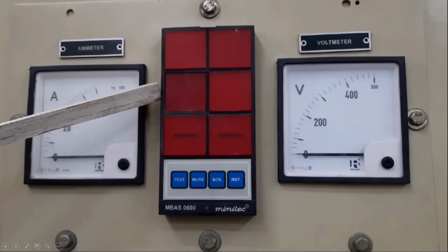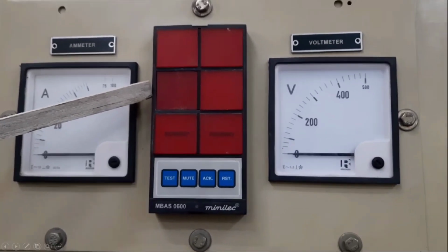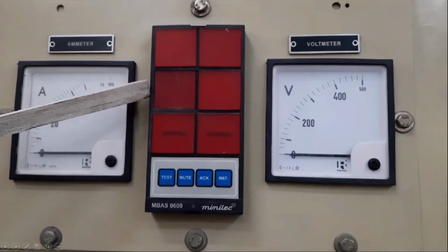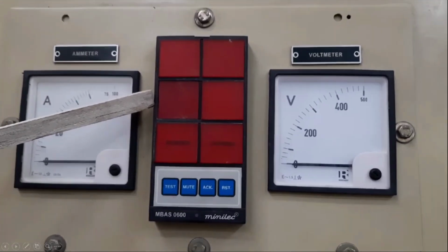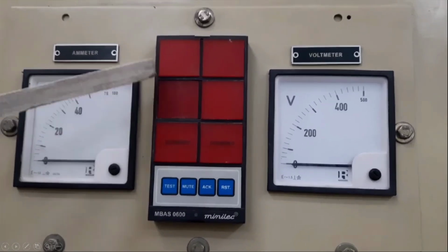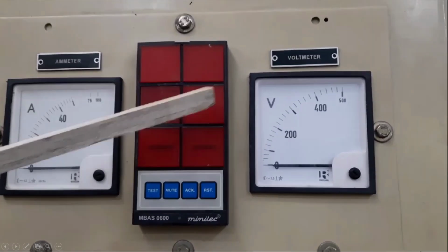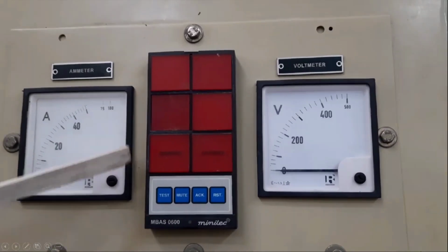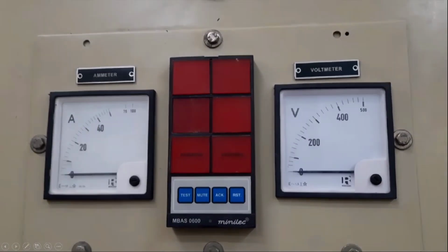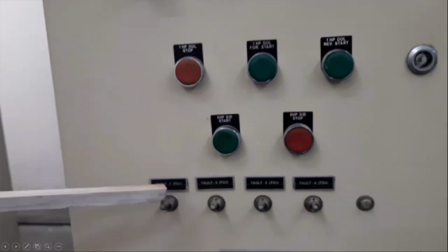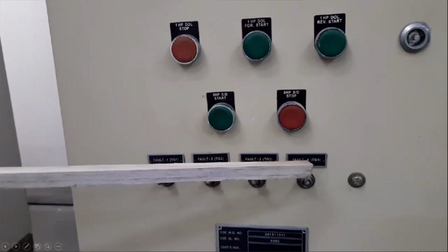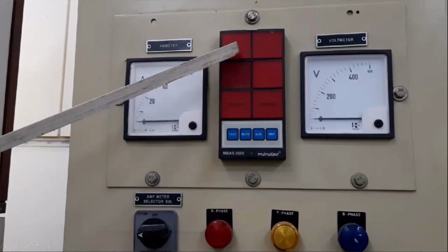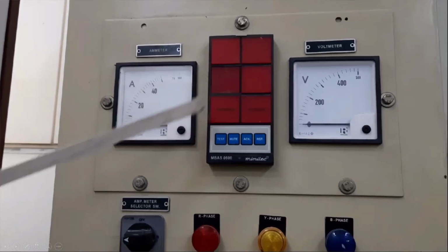Whenever there is a fault in the machine, the operator must know what is the type of fault, and at that time the panel should not work or the motor should stop. So whether the fault is there or not, that will be indicated by these windows. In our system we are creating the fault artificially, and to create that artificial fault we are using these 4 toggle switches. So these 4 toggle switches will be turned on, and these 4 windows will be glowing, and it means that there are 4 different faults which are created.